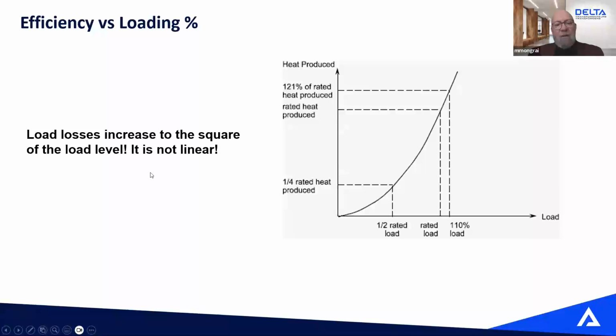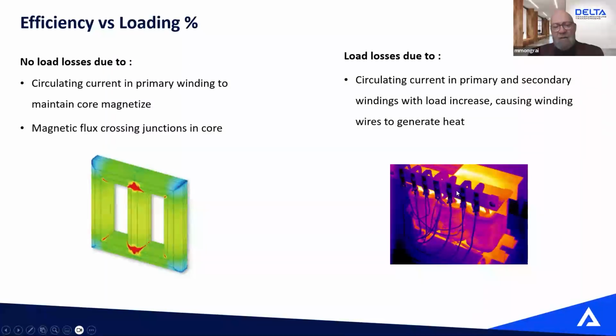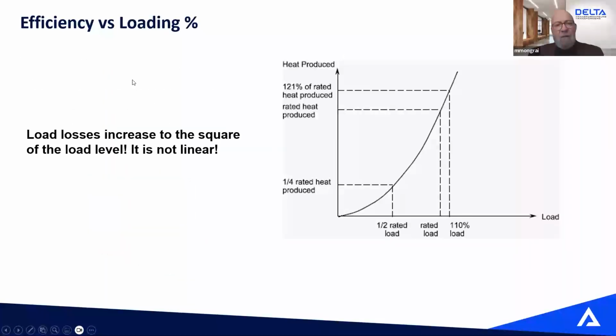And please remember that the load losses, the losses in the winding, they're not linear, they're exponential. So the more you load, the less you are efficient. So at 50%, you generate 25% of your loss because they increase to the square of the load. So 50% load, so 0.5 times 0.5 equals 0.25.